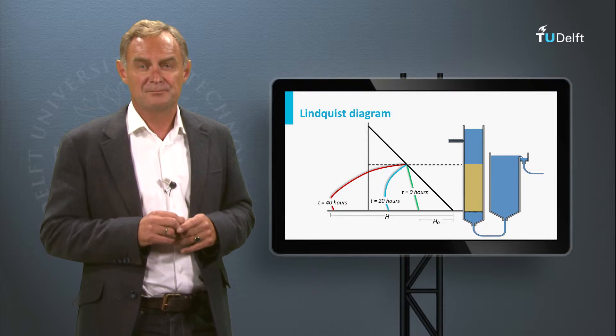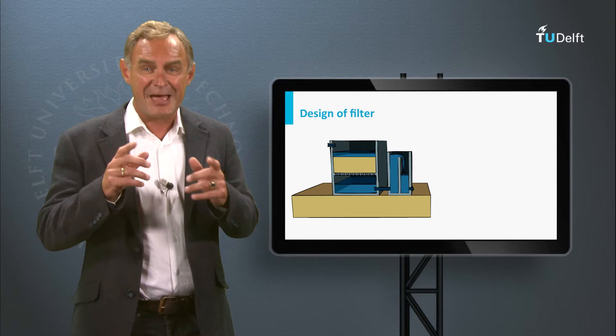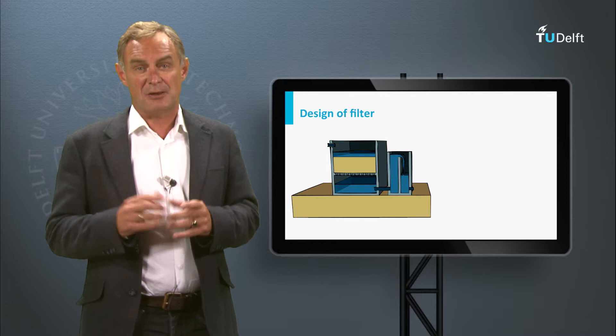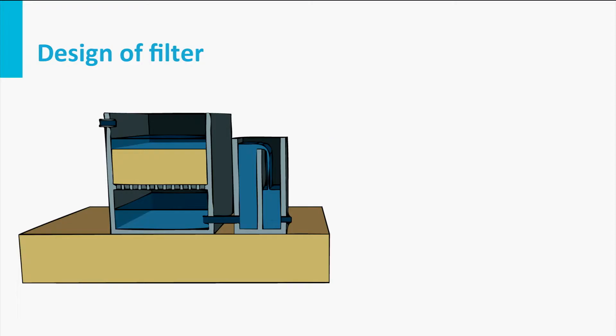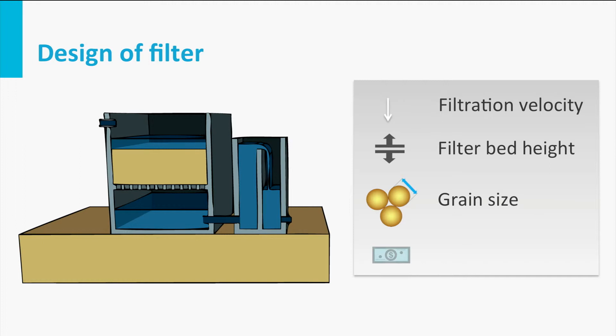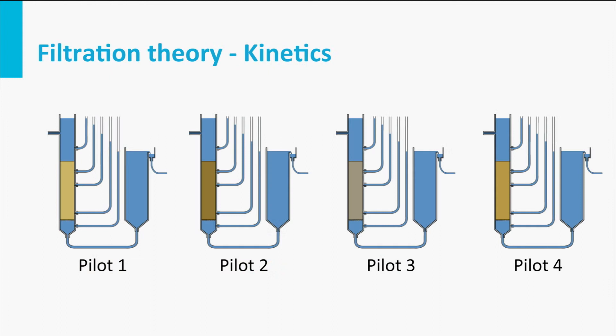For the design of a filter, an optimum must be found such that at the end of the filter run time, the water quality still meets high standards, while the maximum allowable filter bed resistance is reached. Typical filter run times are 1 to 2 days. Different combinations of filtration velocity, filter bed height, and grain size can fulfill these requirements, and economic factors determine the final design.